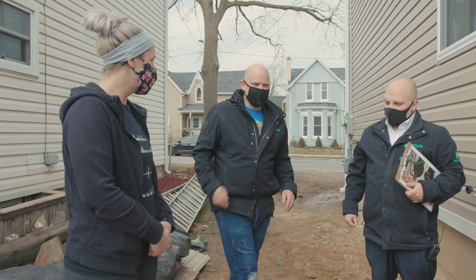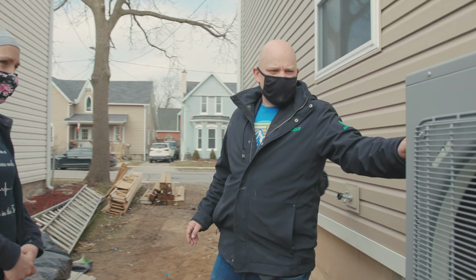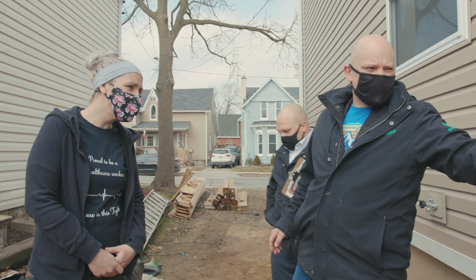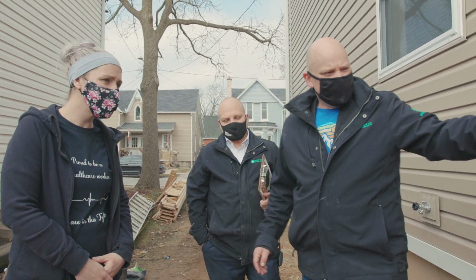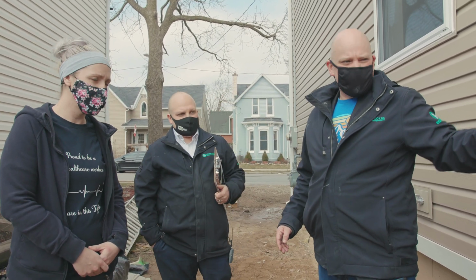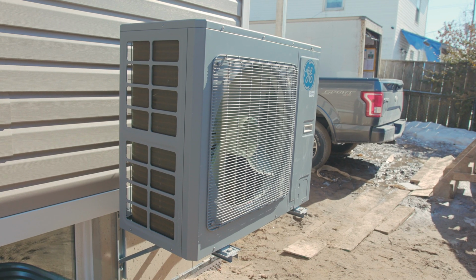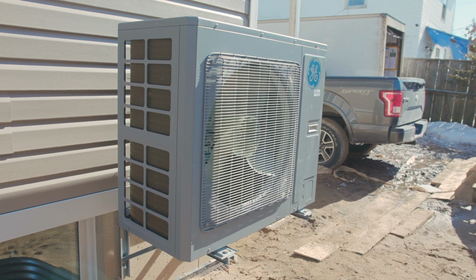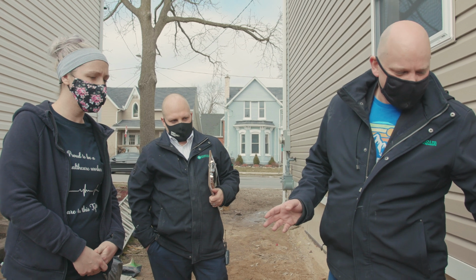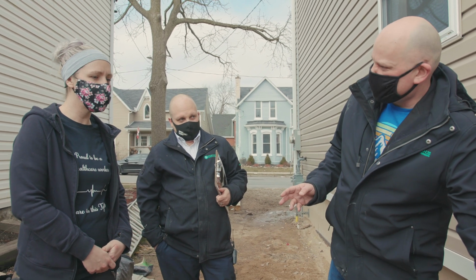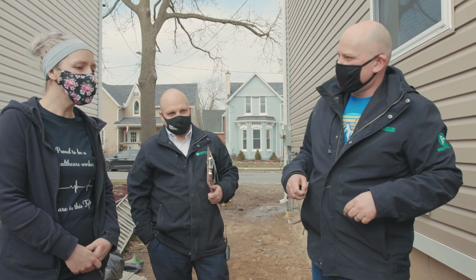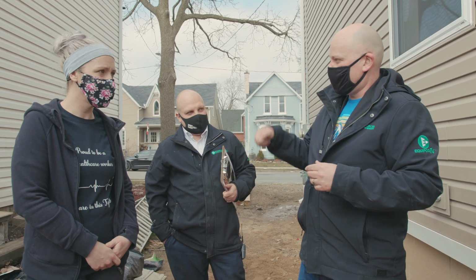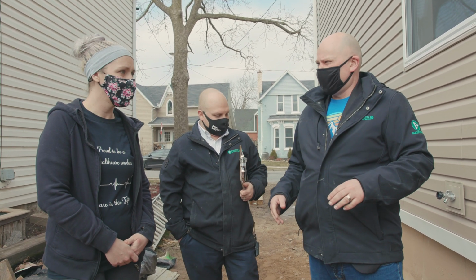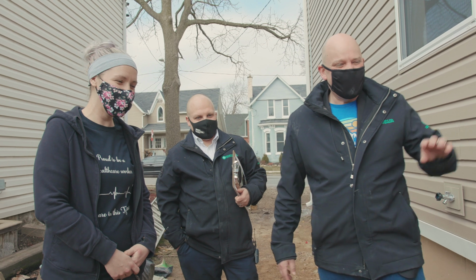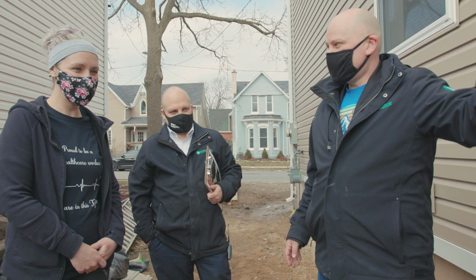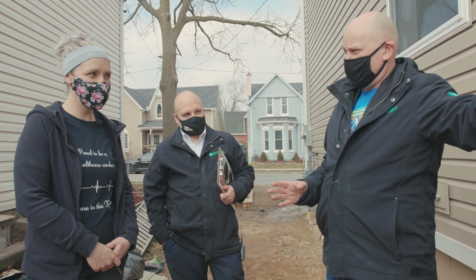So the fins themselves are very thin pieces of metal. So when you are spraying them down, it's good to keep about 6 to 8 inches away so that you don't cause any bends to these fins here. And it's advisable to make sure that you don't have anybody coming in and running their hands over this to create those little dents. If that does happen, you can fix that with a comb, but we try to avoid that as best we can. Yes.